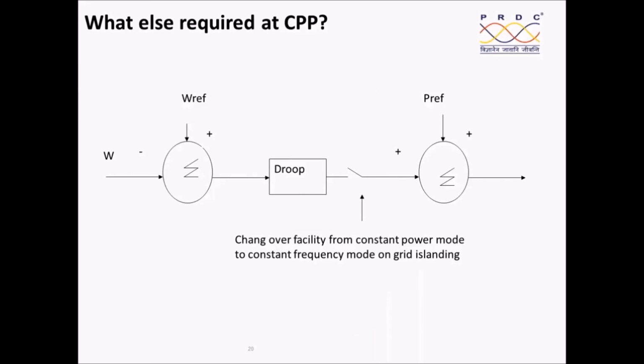There are 2-3 other essential things that are very important when we get islanded. One is, normally the captive power plants, CPPs, will be operating in the constant power mode. What does it mean? I am not in the free governing mode, or I don't want to change my power for the frequency variation in the grid. Therefore, the machine governor characteristic, that is the frequency control, will not come into the picture.